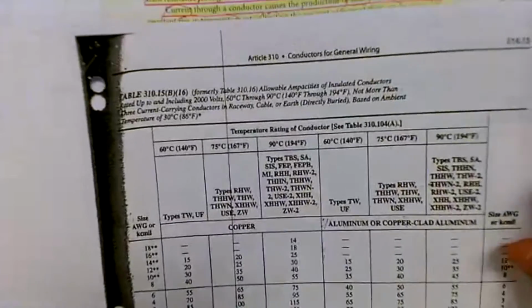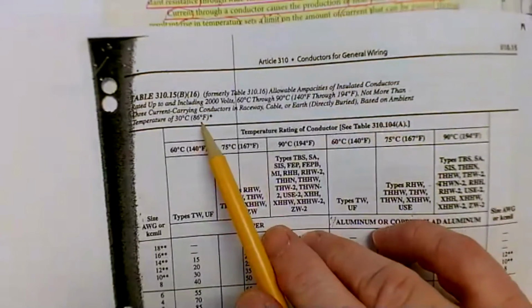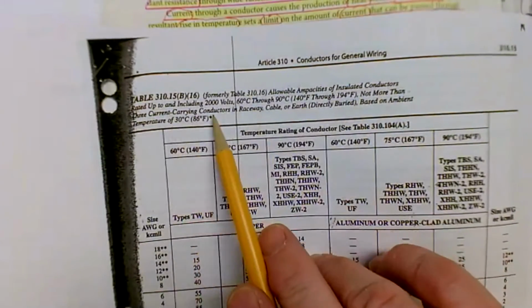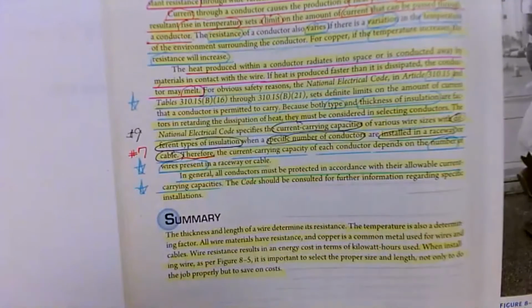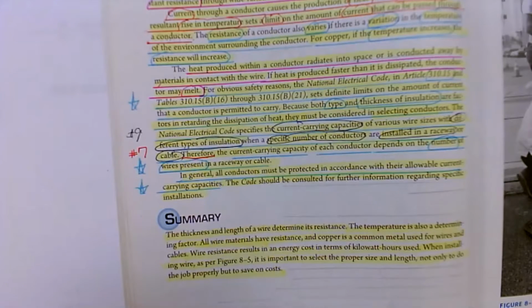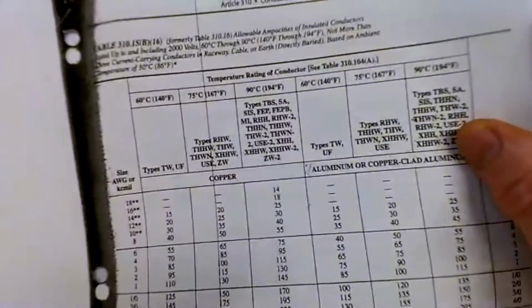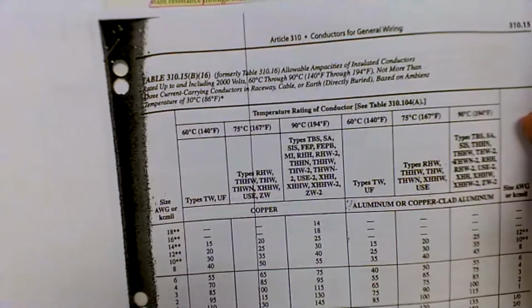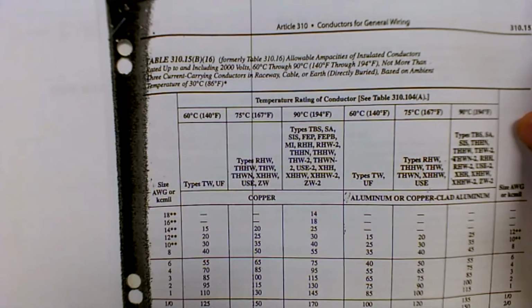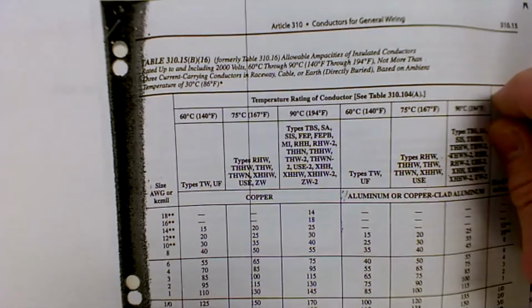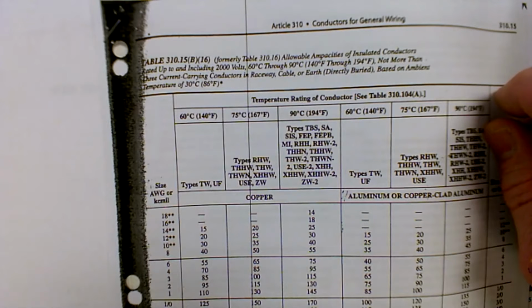Now, you go back to that wire chart, and what does it say at the top? It says at the very top that not more than 3 current carrying conductors in a raceway or cable. You see up in here? Everybody right up in here? Not more than 3 wires in a raceway. So if you got a continuing circuit though, like we run the fan motors, and it all runs through that gray PVC. Right. So really, to pick that up, you need to know what type of insulation you got, and also how many conductors you got, and then you drop down and use those 2 other charts that you showed us.